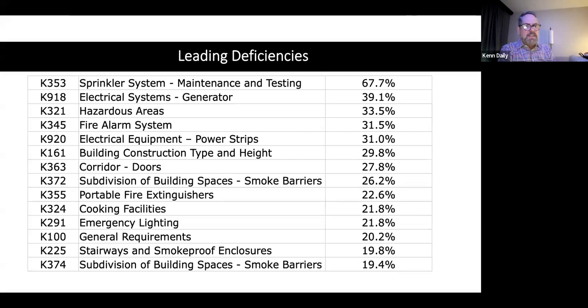Then corridor doors, remember, every door to the corridor must close and latch. Every door to the corridor must close and latch, regardless of the type of door, whether it's a storage door, closet door, resident room door, office door. And they have to be a 1 3/4 inch solid wood core door, or like and similar, could be a metal door, could be a 20-minute fire rated door, has to resist the passage of smoke. But the biggest issue is closing and latching.